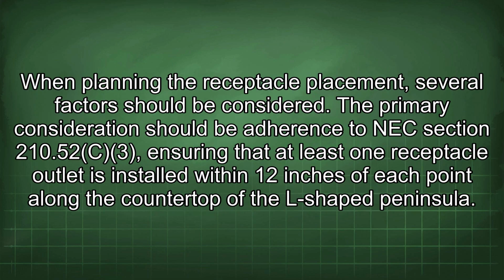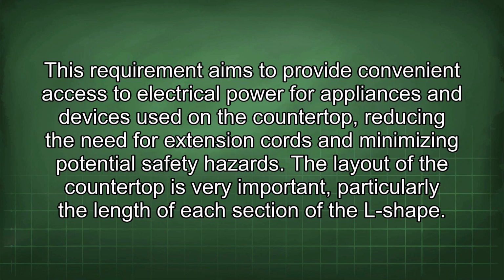When planning the receptacle placement, several factors should be considered. The primary consideration should be adherence to NEC Section 210.52(C)(3), ensuring that at least one receptacle outlet is installed within 12 inches of each point along the countertop of the L-shaped peninsula. This requirement aims to provide convenient access to electrical power for appliances and devices used on the countertop, reducing the need for extension cords and minimizing potential safety hazards.